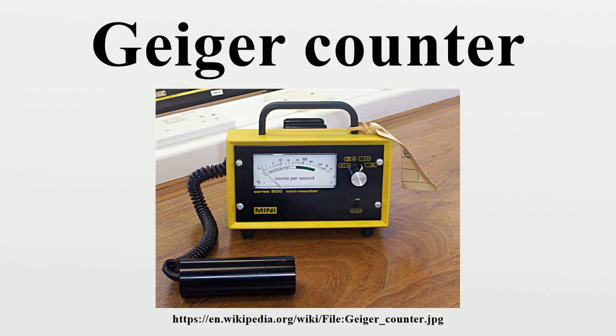The guide does not recommend the GM detector for mixed alpha and beta contamination detection, and they are only recommended as satisfactory for beta-only contamination. However, for gamma and low-voltage X-rays they are recommended as the best instrument type.